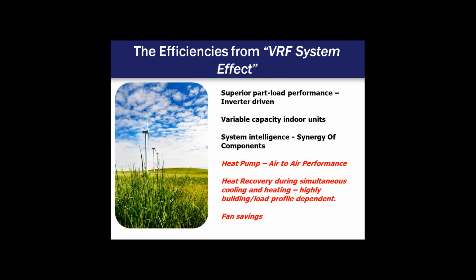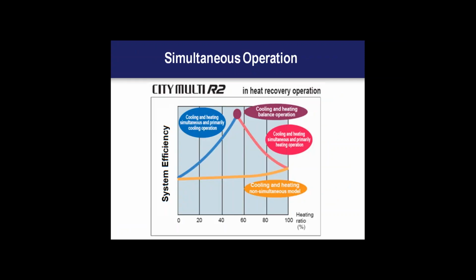Second, the heat recovery during simultaneous cooling and heating. The thing to point out is the ability to recover heat not just during cooling dominant modes, but also during heating dominant modes, and that's distinct and different from other conventional systems. And lastly, the fan savings tends to be one of the bigger components, as I mentioned before.